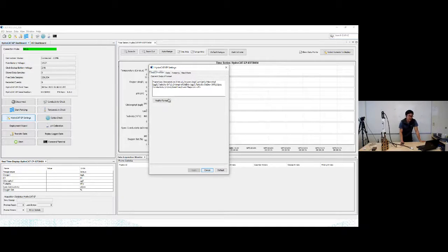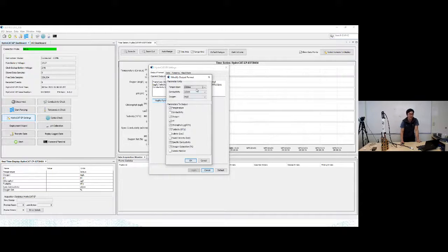Output format allows us to modify the format that the instrument is outputting in real time. So when we click on this, we can pick our units for temperature, conductivity, and oxygen. And we can also choose which parameters we want to output, say, to a data logger or to UCI. And so currently it's configured to output temperature. Let's turn it to output conductivity, oxygen, pH, chlorophyll, turbidity.